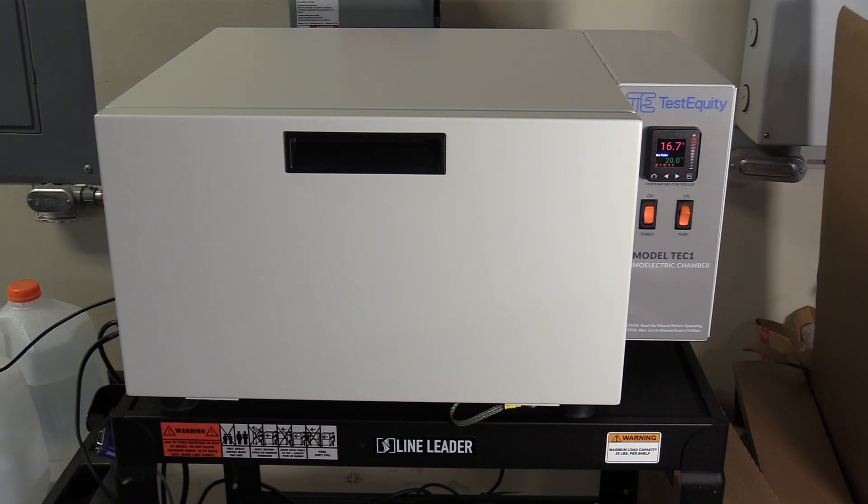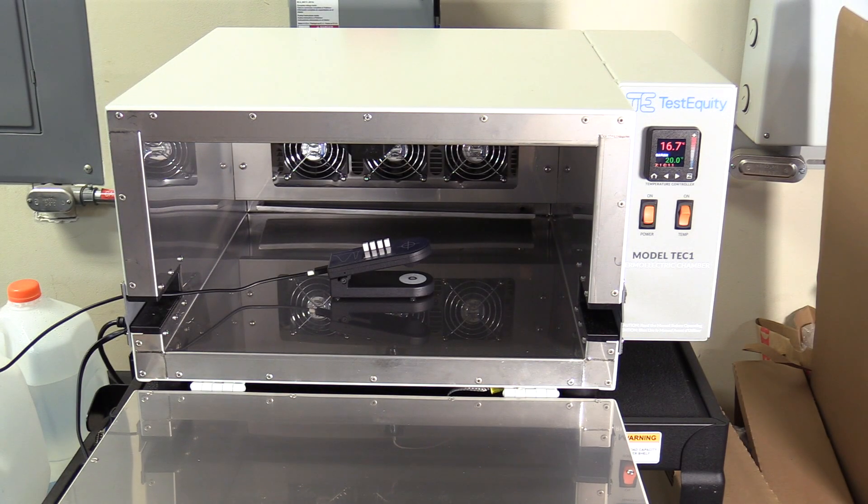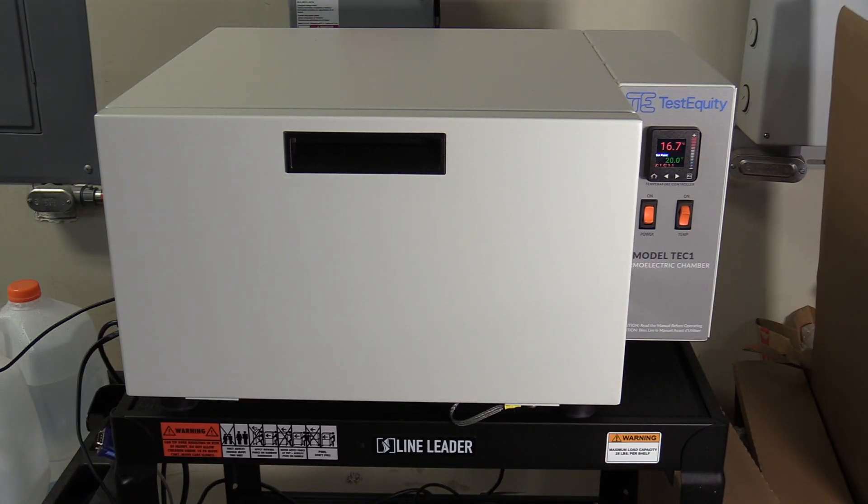To support that, I've acquired this thermal test chamber. The device under test is placed inside the chamber, and the chamber has a controller which can be computer controlled, where the chamber will ramp in a very controlled fashion across a full range of operational temperatures, and I will be able to collect all the data to build a full temperature profile of the device. With this profile, I can then correct the readings such that a UV-Vis densitometer should read exactly the same whether it is 10 degrees Celsius in your room or 30 degrees Celsius in your room.